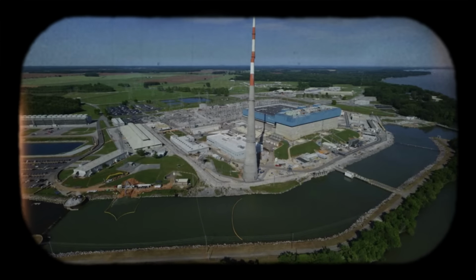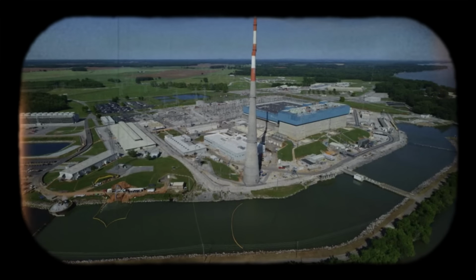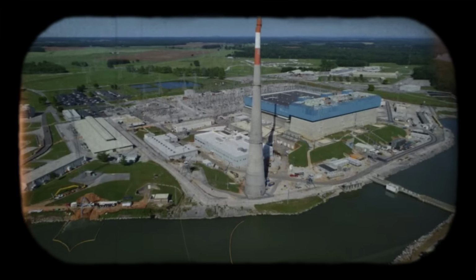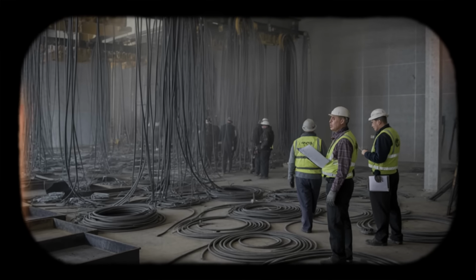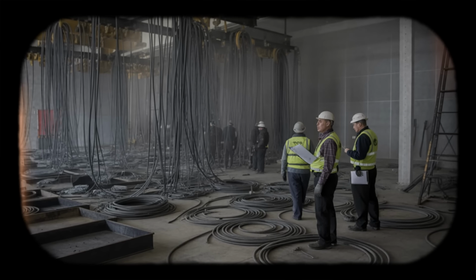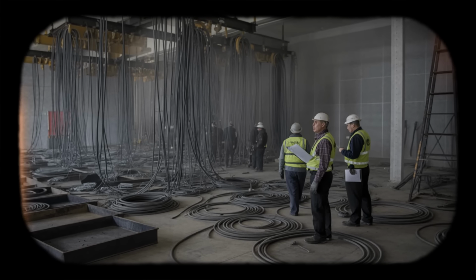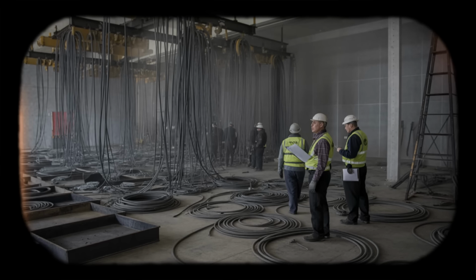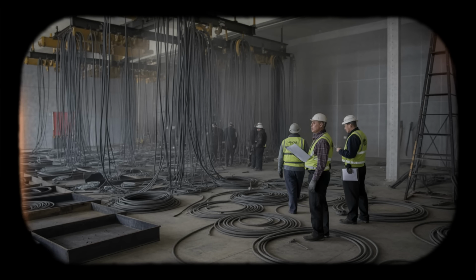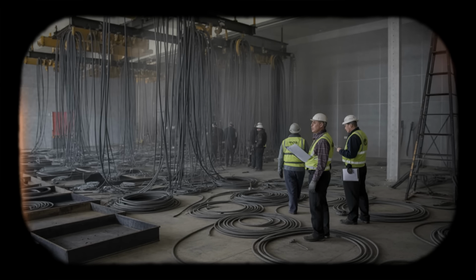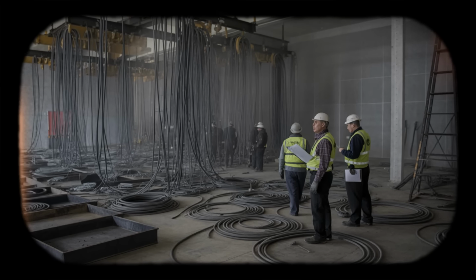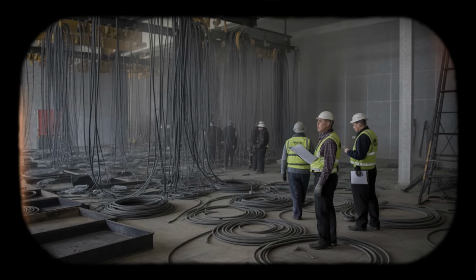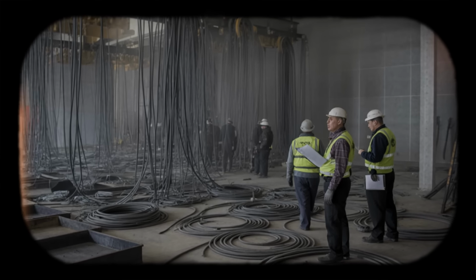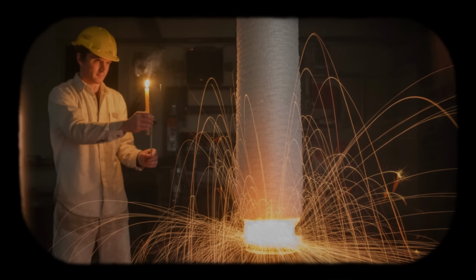Residual heat removal pumps face similar problems. RHR is critical during shutdown conditions because decay heat continues to be generated even after control rods are fully inserted. About 4 to 6% of full thermal power persists as unstable fission products decay. This heat must be removed continuously, or core temperature will rise to damaging levels. RHR pumps circulate coolant through heat exchangers, transferring decay heat to the service water system.